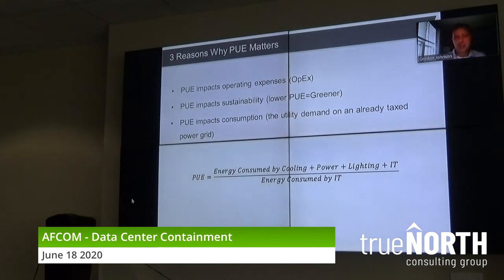I will say it's simple to cheat on the number. Some people only do their measurements in the dead of winter. There are also other things that could make your PUE go up when you're really saving money, so we'll take that out of the equation. But PUE is nice because it gives you a quick look at how energy efficient your data center is. And after you make changes, hopefully you'll see from the PUE that it's even more efficient.